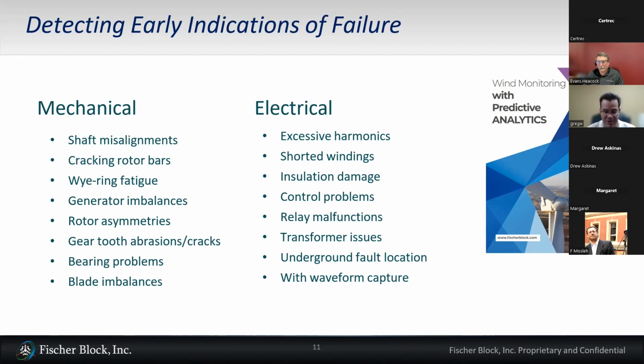It's basically the flux across from the stator to the rotor, and that flux gets distorted and it shows up in the signal. So yes, both mechanical and electrical elements of the system affect the electrical signal. So many times when we're measuring vibration with our vibration sensors on a piece of rotating equipment, we'll be able to correlate with high correlation between the vibration signal and the electrical signal and see the same frequency distortions. But those faults that don't vibrate, we can pick up in the electrical signal where a vibration plot would not. So it's interesting to see electrical and mechanical component degradations show up in the electrical signal.